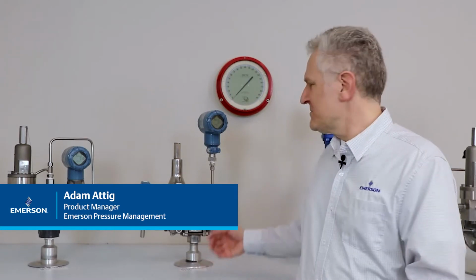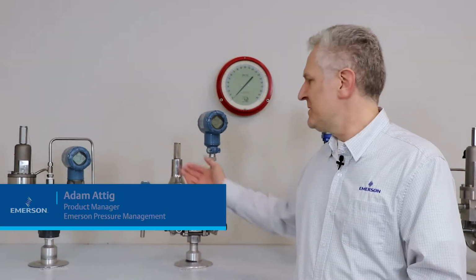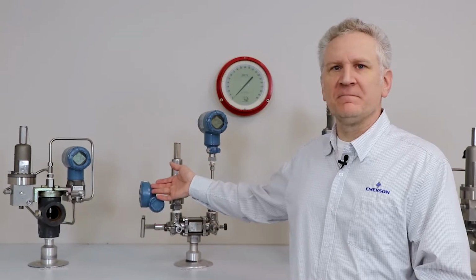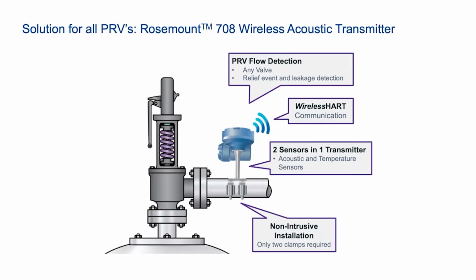The next example of a modern PRV we will review is the Anderson Greenwood 80 series and the Rosemount 708 acoustic transmitter. The Rosemount acoustic transmitter is affixed to the PRV's outlet piping and measures sound levels in the pipe that occur with a valve opening or closing, as well as any temperature change due to flow during an overpressure event. The transmitter will provide time-stamped notification when the release is occurring and when the release has stopped.